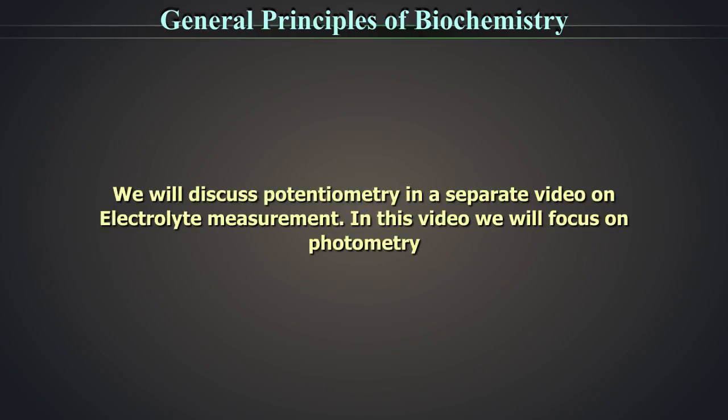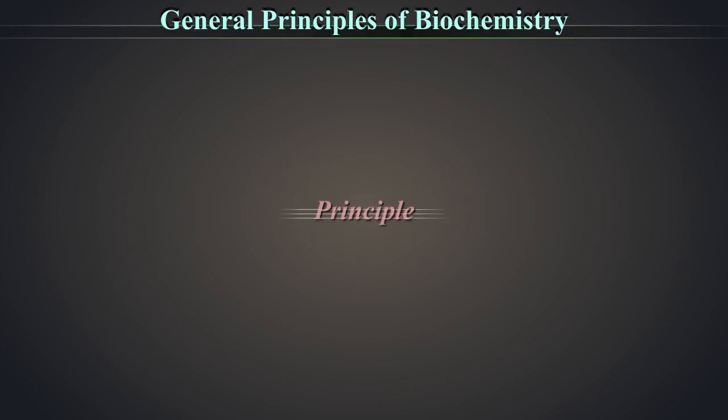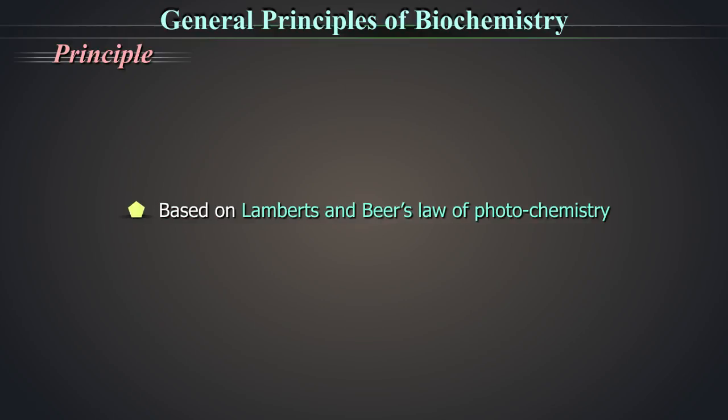We will discuss potentiometry in a separate video on electrolyte measurement. In this video, we will focus on photometry. The principle of operation of a biochemistry analyzer is based on Lambert's and Beer's law of photochemistry.